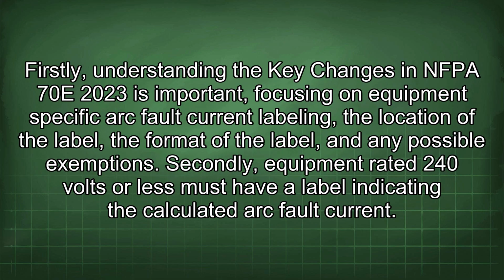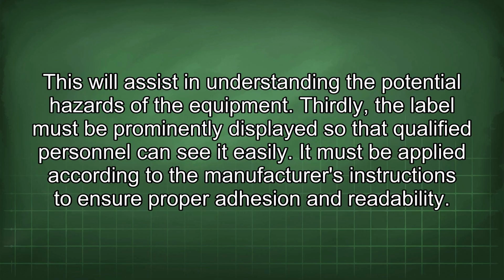Firstly, understanding the key changes in NFPA 70E 2023 is important, focusing on equipment-specific arc fault current labeling, the location of the label, the format of the label, and any possible exemptions. Secondly, equipment rated 240 volts or less must have a label indicating the calculated arc fault current. This will assist in understanding the potential hazards of the equipment. Thirdly, the label must be prominently displayed so that qualified personnel can see it easily. It must be applied according to the manufacturer's instructions to ensure proper adhesion and readability.